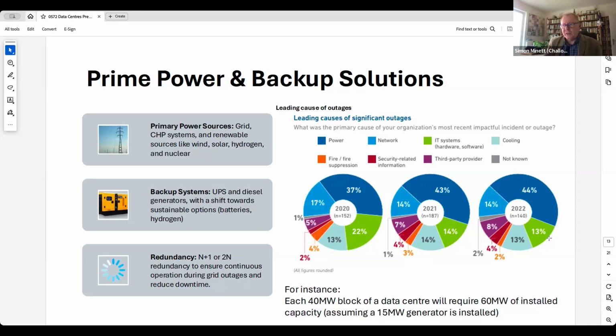Finally, it's a question of redundancy. If you go for a prime power system, you need a large level of resilience. So if you take a 40 megawatt block of a data center — they're generally modular, so that's a reasonable size of power demand — that will require around 60 megawatts of installed capacity to give you that redundancy, that resilience in the system.